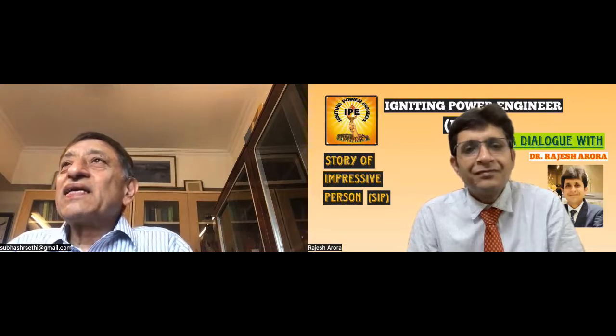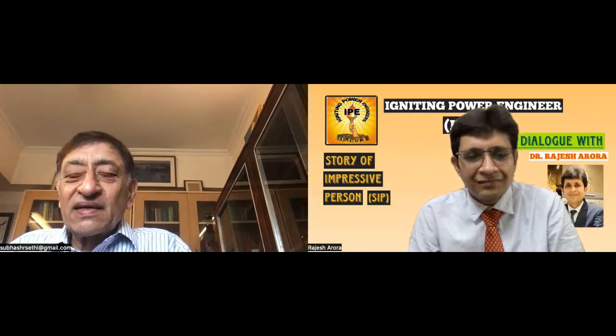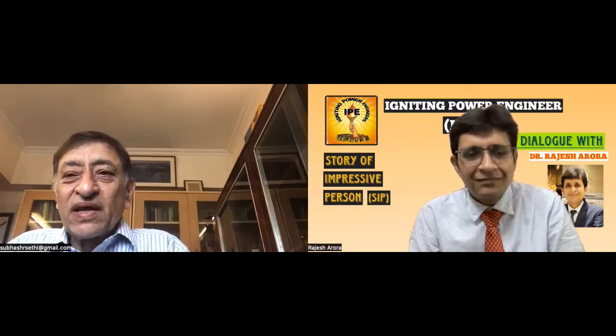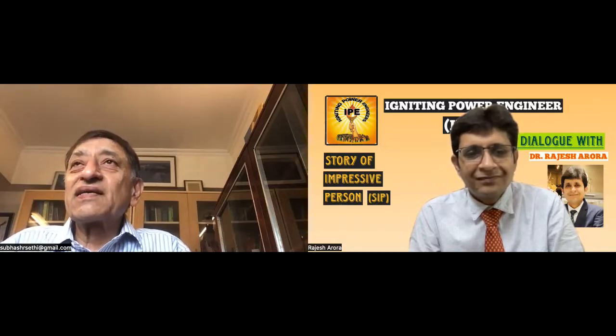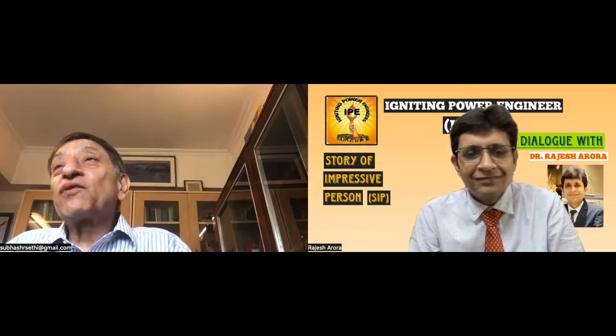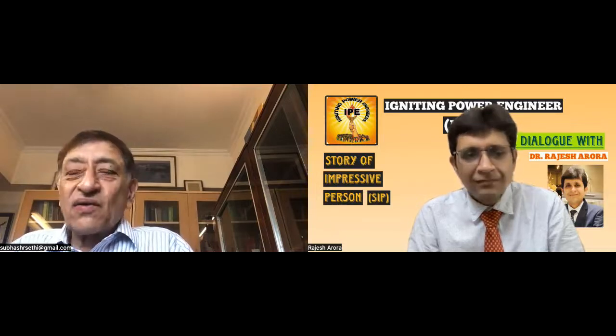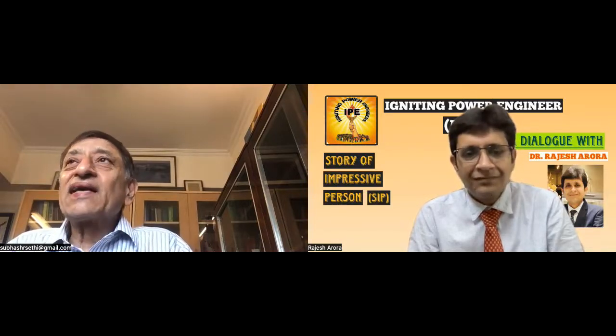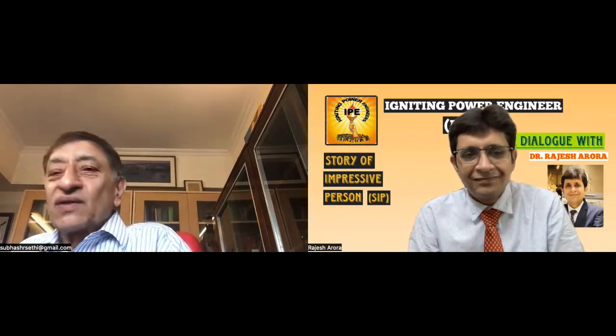Piling was necessary because of the ash field area—the turbine foundation had to be on piles, and so was the transformer foundation, including the foundation of the breakers and other things in the switchyard. These were vibro-flotation piles, which was very unique. With water pressure, you make a hole of about 3 meters and dump stone ballast of size 6 to 8 inches into that, and thereafter cover it up and make your foundation on that.